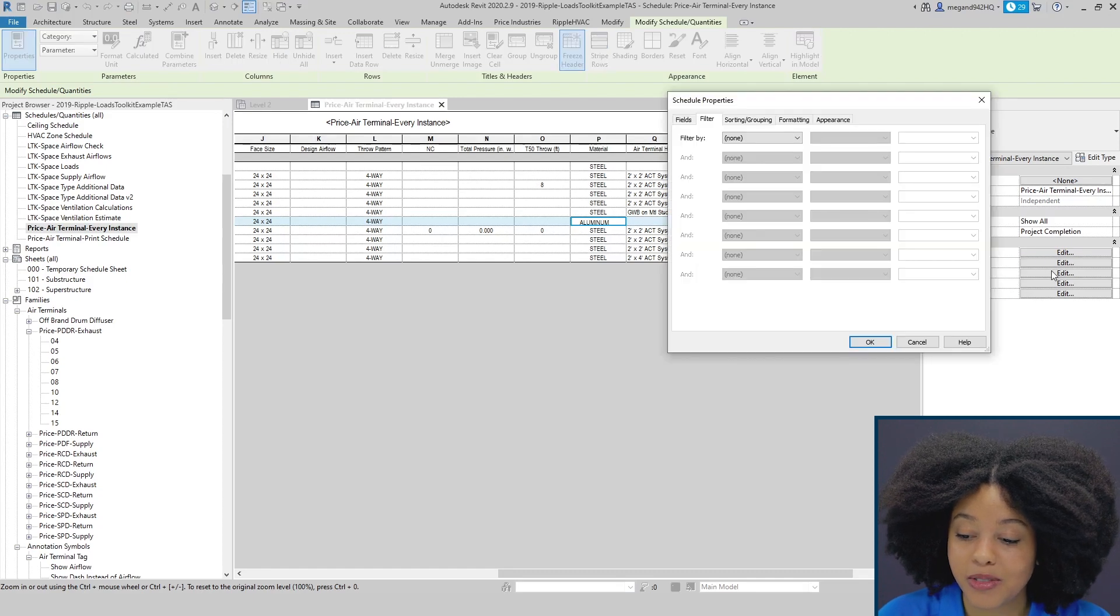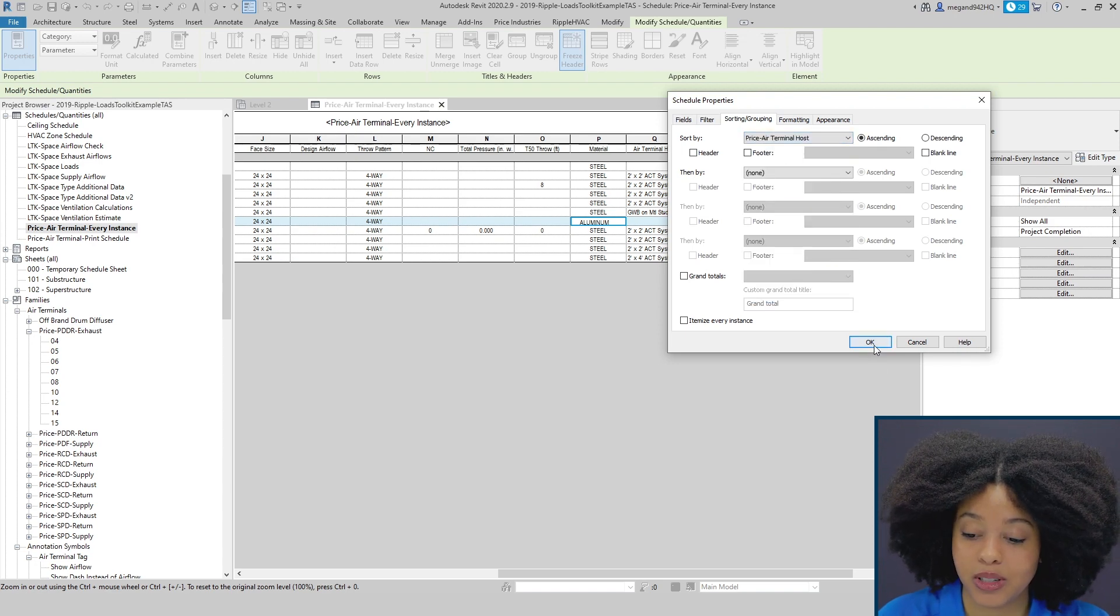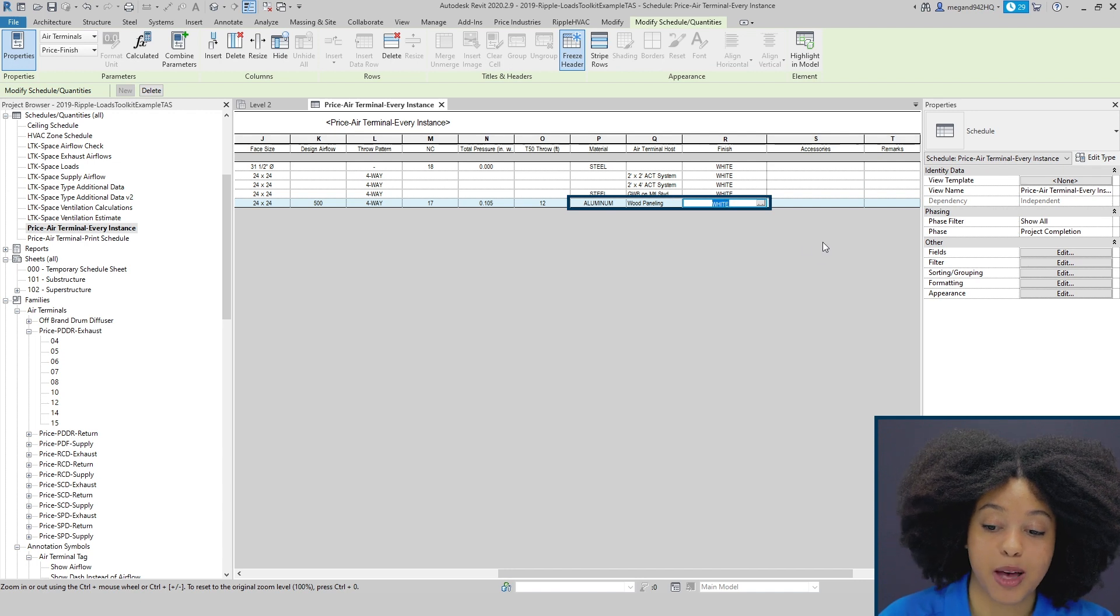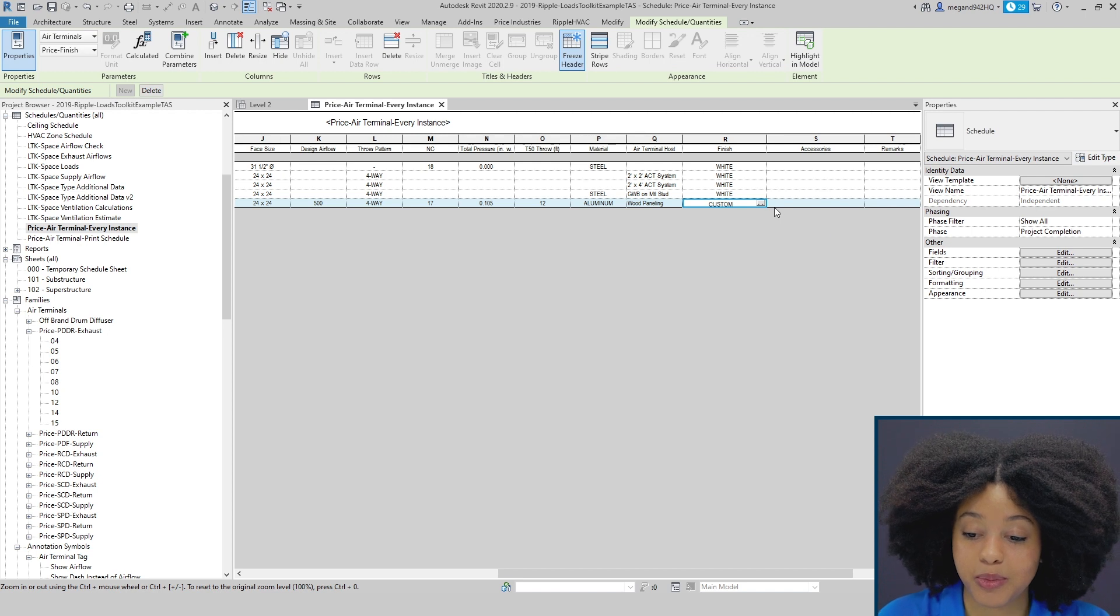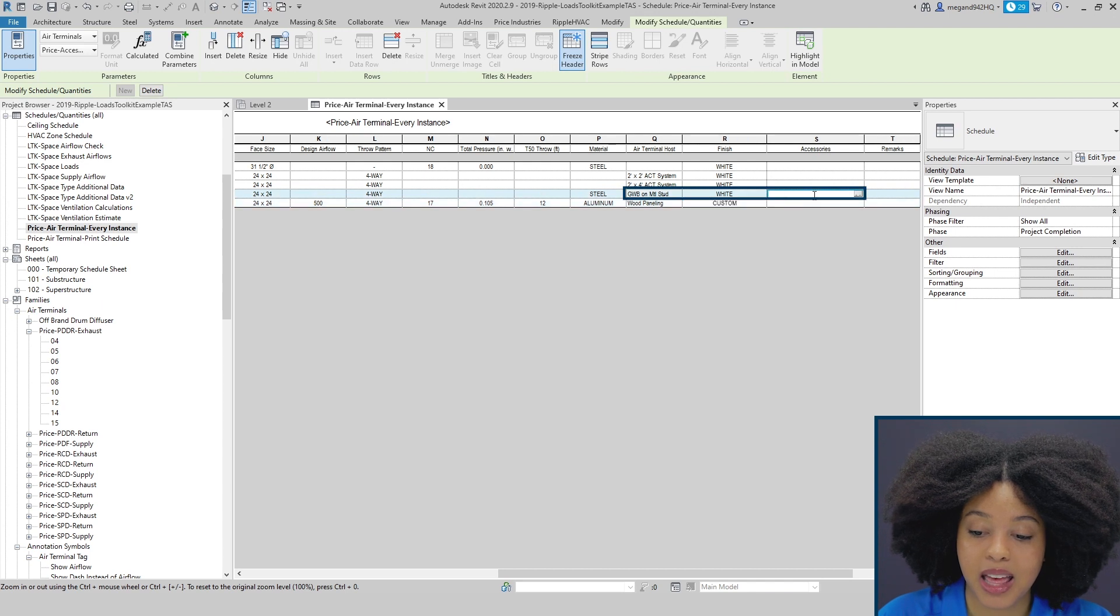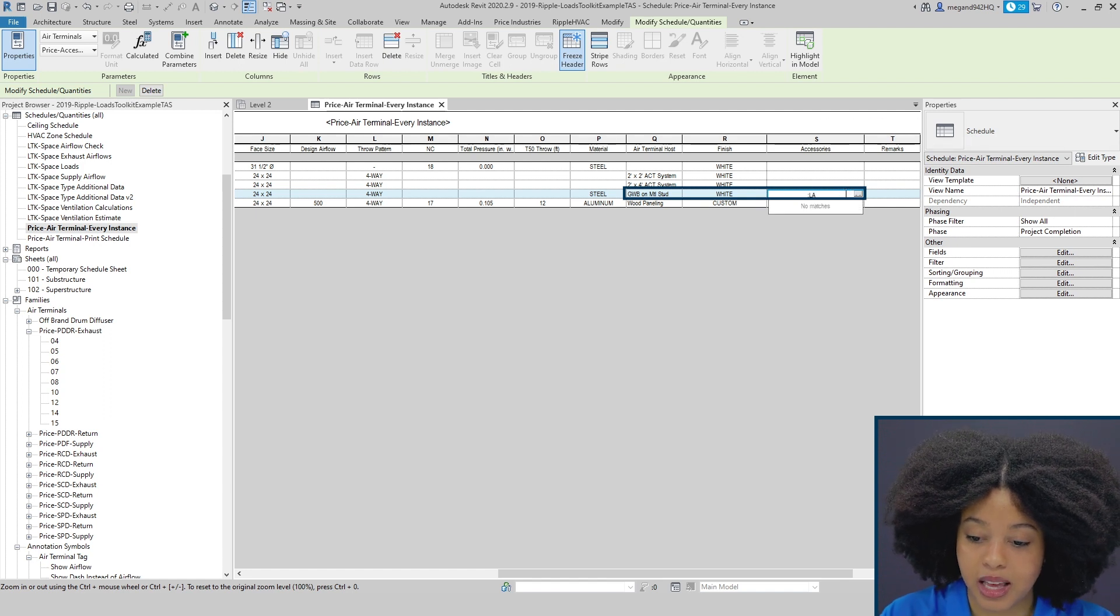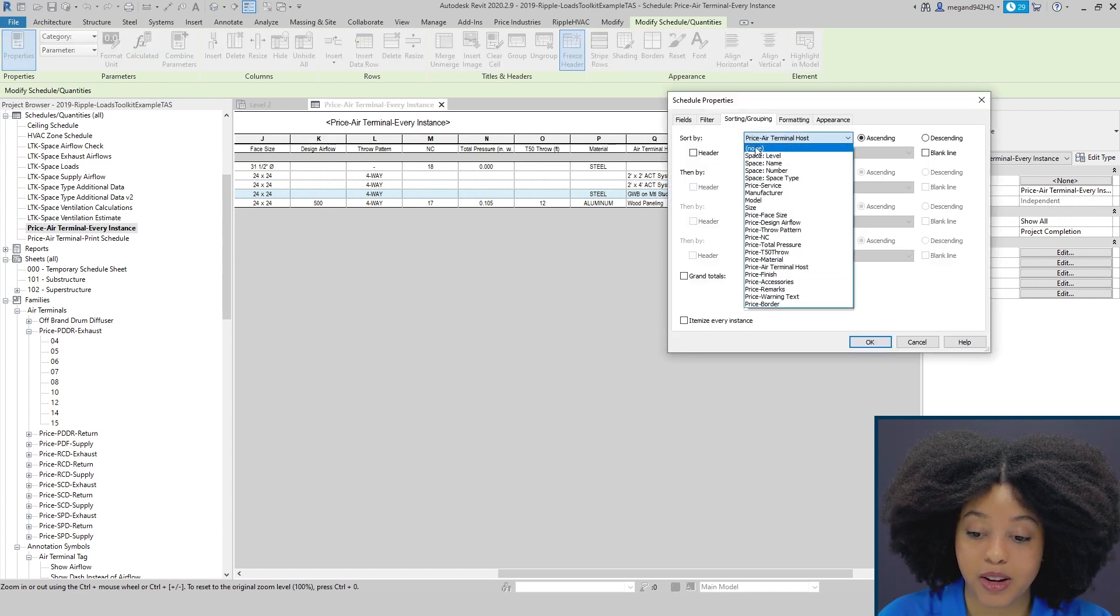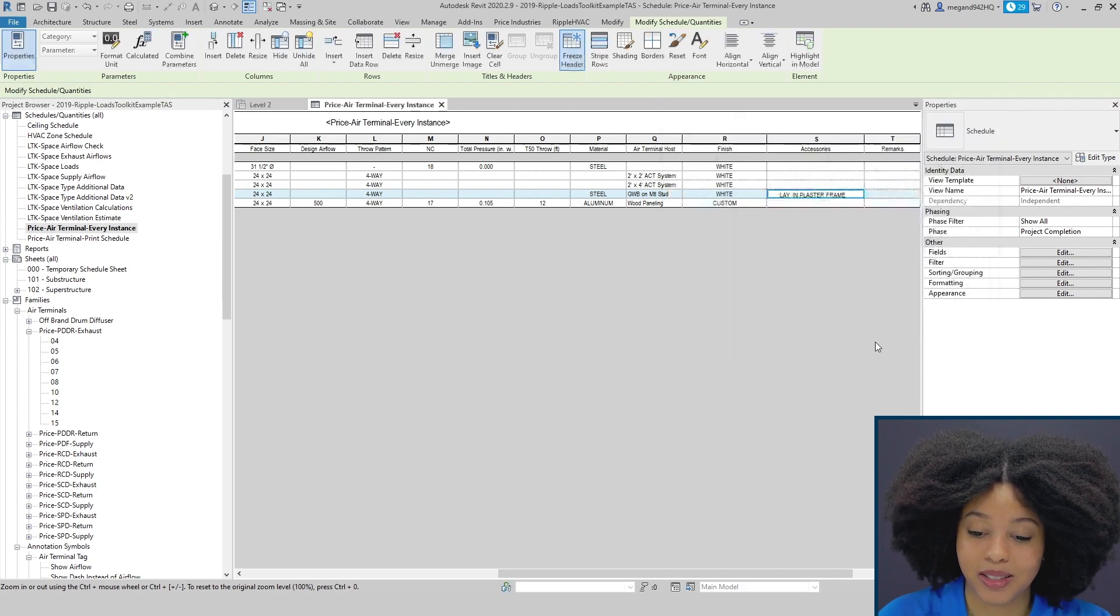Another benefit of the grouping and filtering is to sort by your air terminal host. Here we can see we have an example of a wood panel ceiling. This is a prime example where we may know that we want a custom finish rather than white. We can also utilize the accessories. Here we have a gypsum ceiling and we may know that we actually want a lay-in application, so we're going to select a lay-in plaster frame. To go back to the itemized list simply sort by none and re-click itemize every instance.